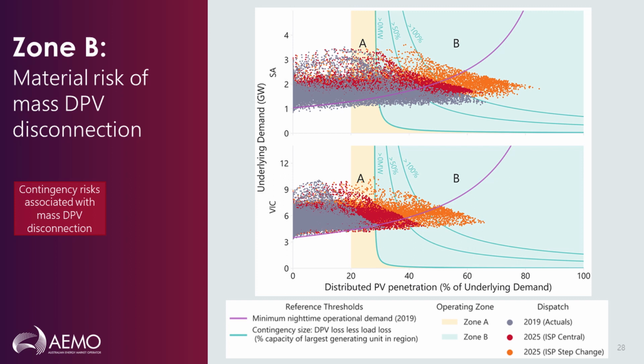Eventually, the net contingency size may become unmanageably large, especially for regions of the NEM that can operate as an island under some conditions. So that's reflected in the other solid blue lines as you move to the right in this picture. The 50% and the 100% are with reference to the largest credible risk that's managed today. Again, over to Taru, who will talk us through a significant challenge in the South Australian region today around the risk associated with DPV systems disconnecting in case of a fault in the Adelaide metropolitan area.